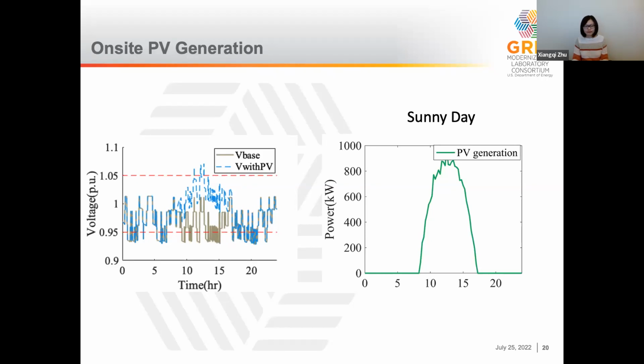This results in some voltage violations, shown here by the blue dashed line in the left figure. The Vbase represents the voltage profile at the connection point of a 3-port charging station at a good location in the realistic utility feeder model we just showed. So this is the voltage base, and the blue line is the voltage with PV. We can see in this period there are some voltage violations, and even though there are no violations in other periods, it can also boost the voltage to a very large extent, which is not desired.